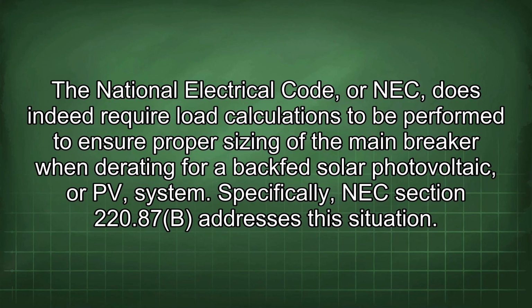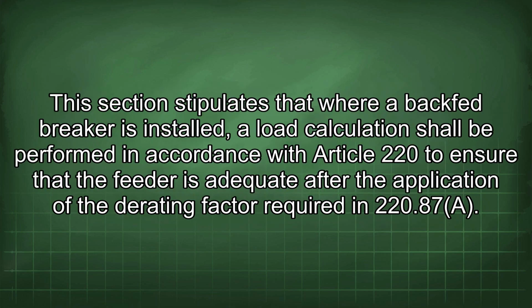The National Electrical Code, or NEC, does indeed require load calculations to be performed to ensure proper sizing of the main breaker when derating for a backfed solar photovoltaic, or PV, system. Specifically, NEC section 220.87(B) addresses this situation.